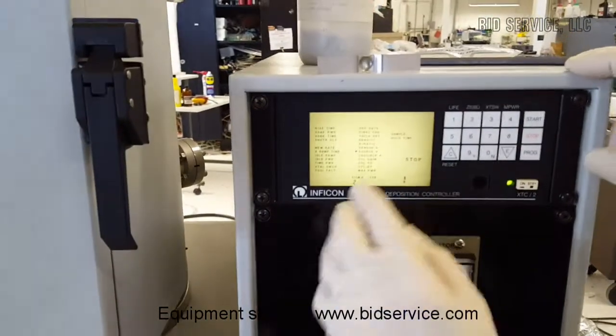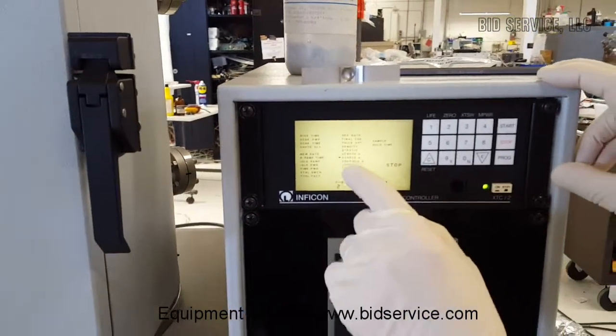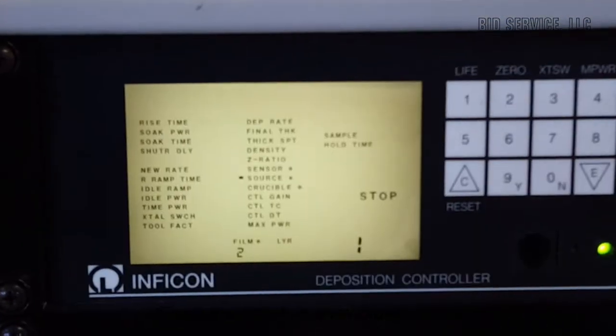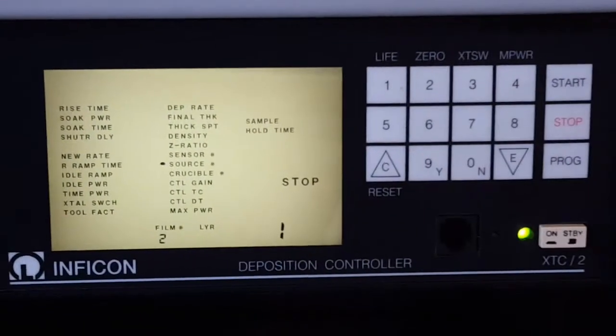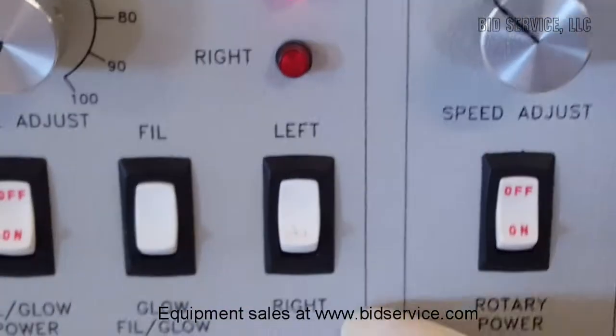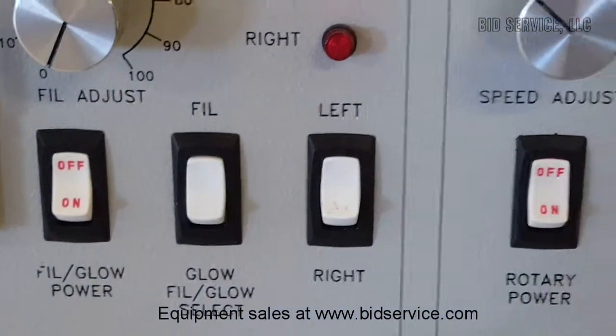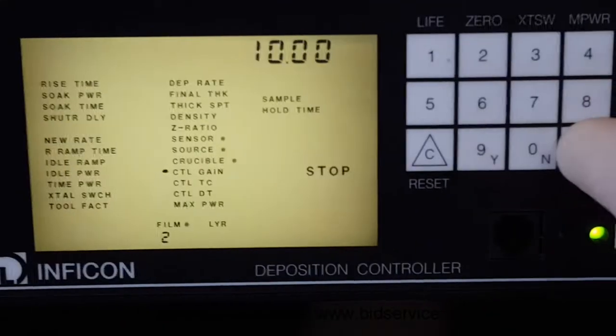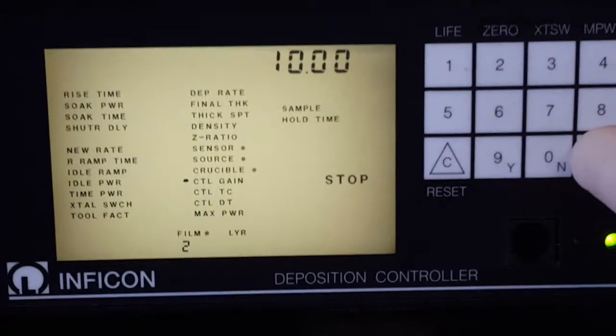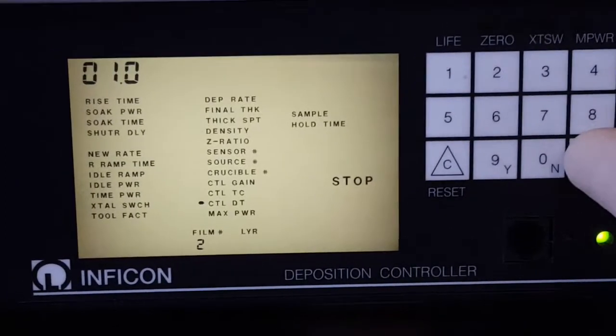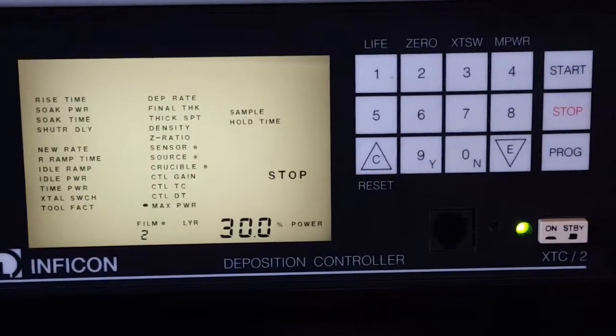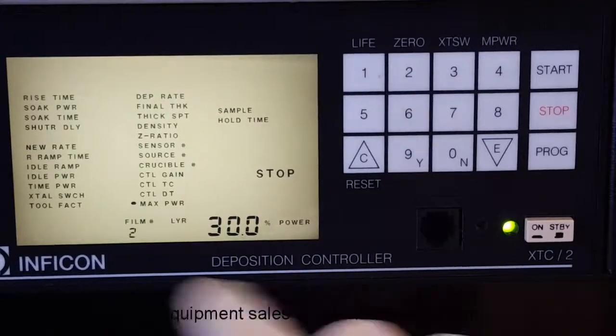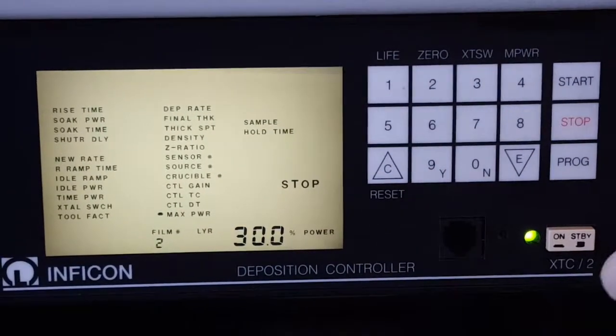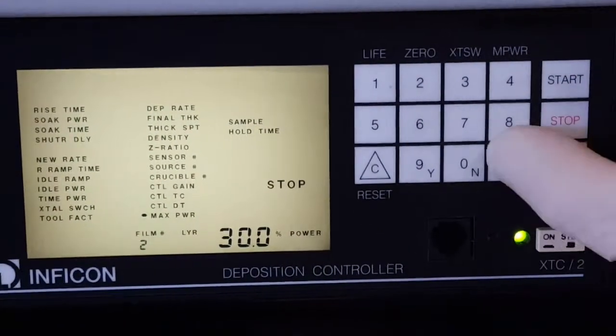Let's get back to here. Again, 1 source. To determine what source is being used for that film, you'd have to use your selector down here, your left or right. Crucible, again, there's no crucible in here. And then here's your PID for controlling your deposition rate, your gain. Again, this is all explained in the manual. Here I have the max power set to 30, so it will not go above 30%.